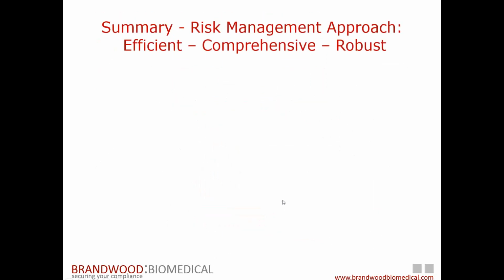So, in summary, a risk management approach provides a framework to conduct a biological evaluation. It causes you to build a comprehensive understanding of your device and the materials contained and any materials which contaminate that device and their interactions, and how to develop a robust knowledge base to establish safety. I remind you, don't fall into the testing trap.